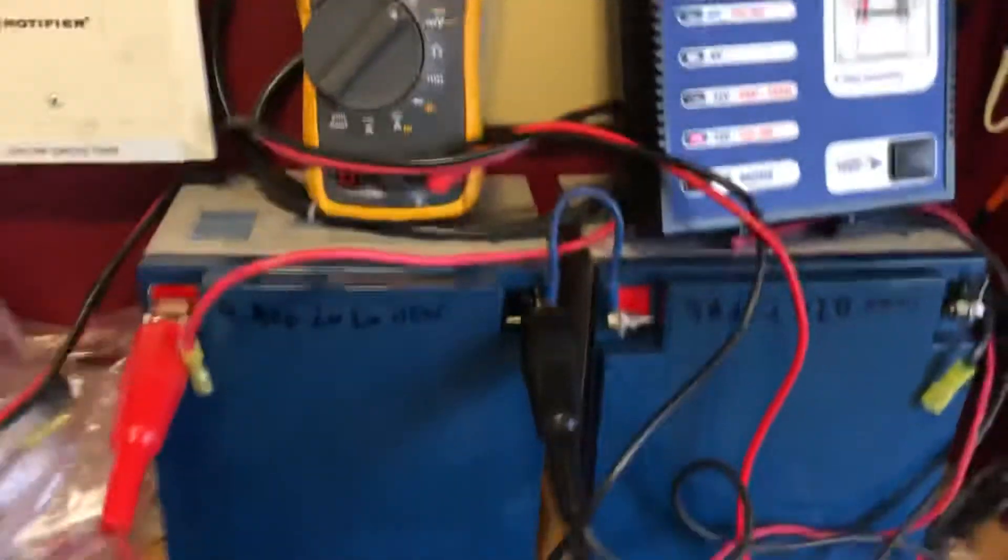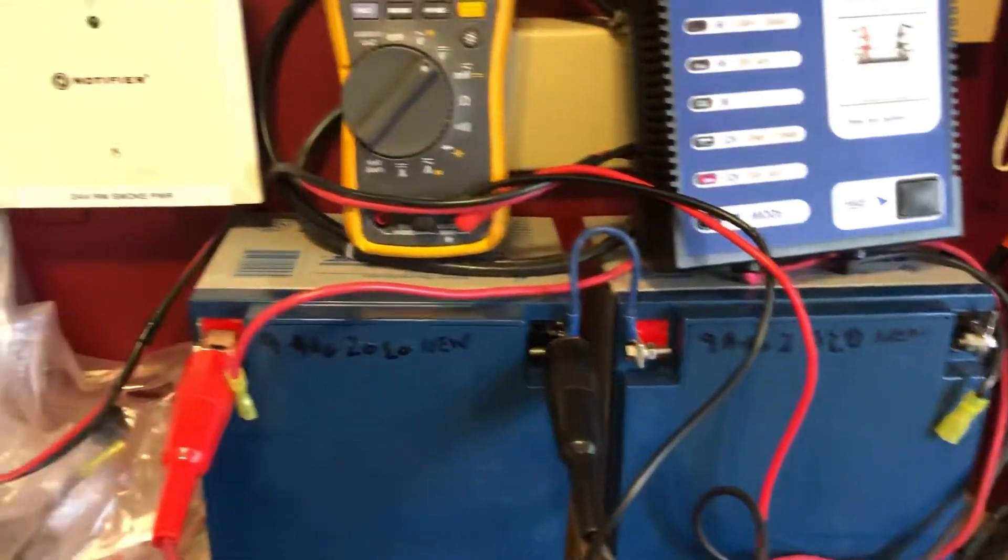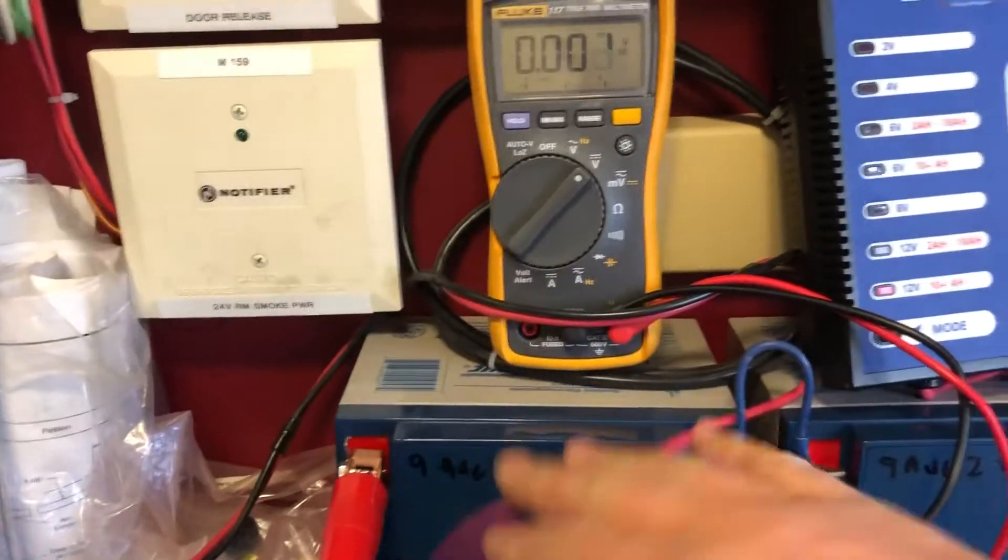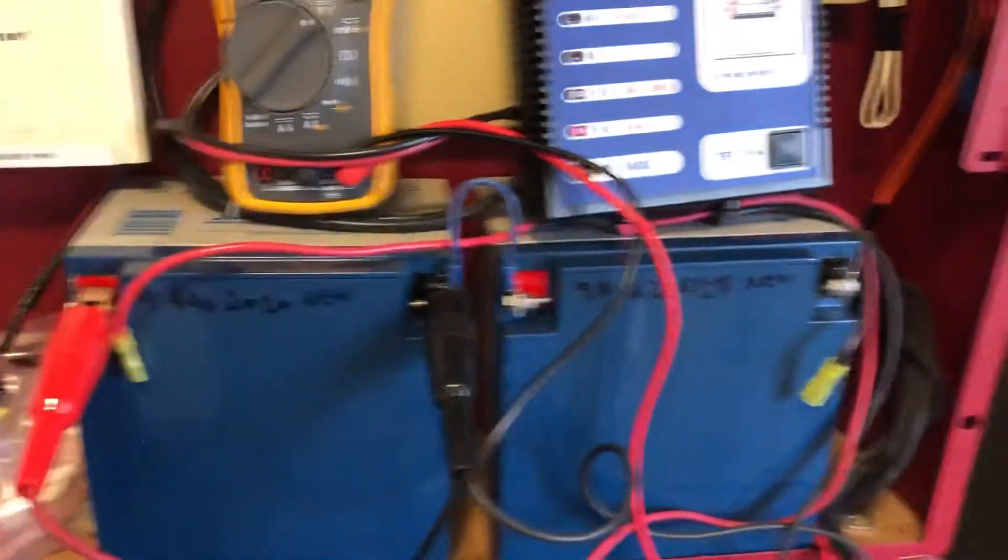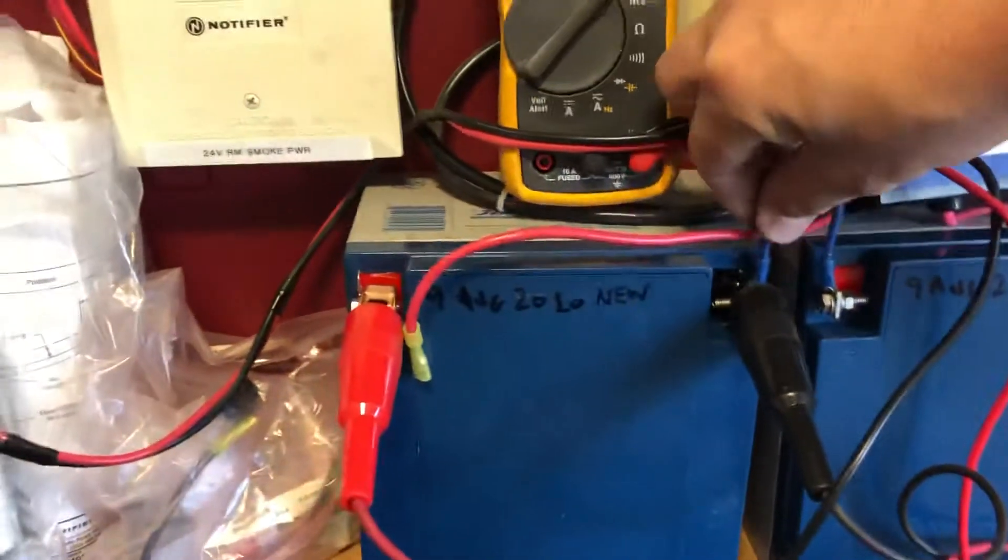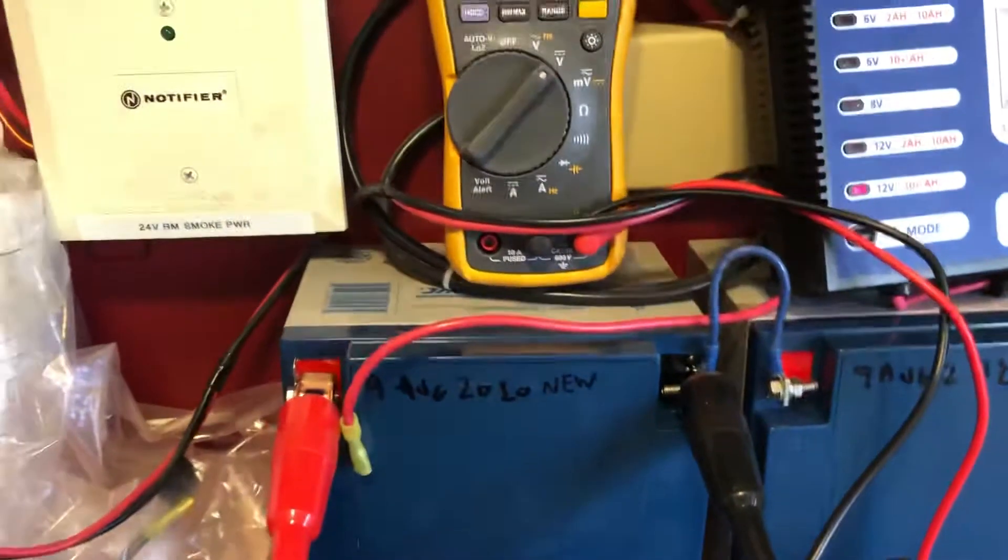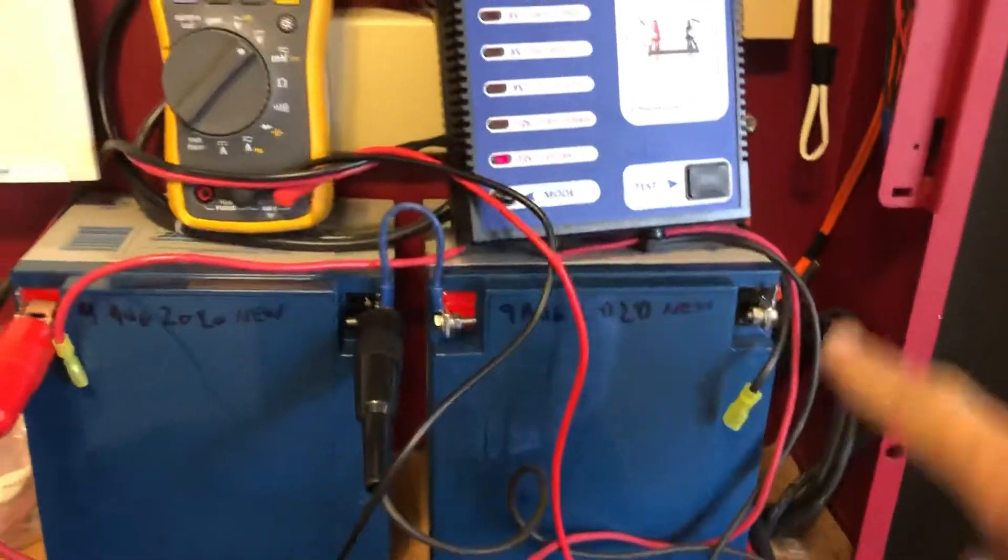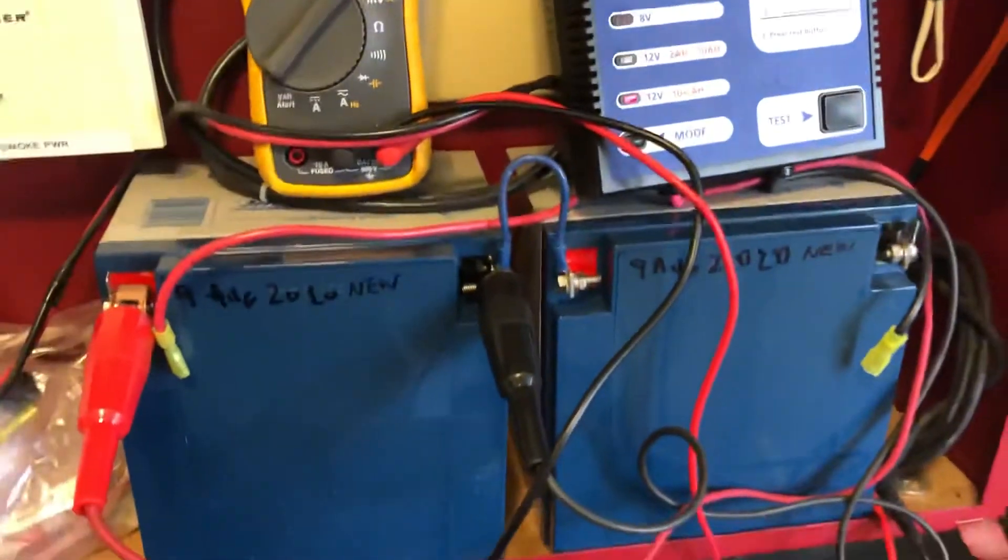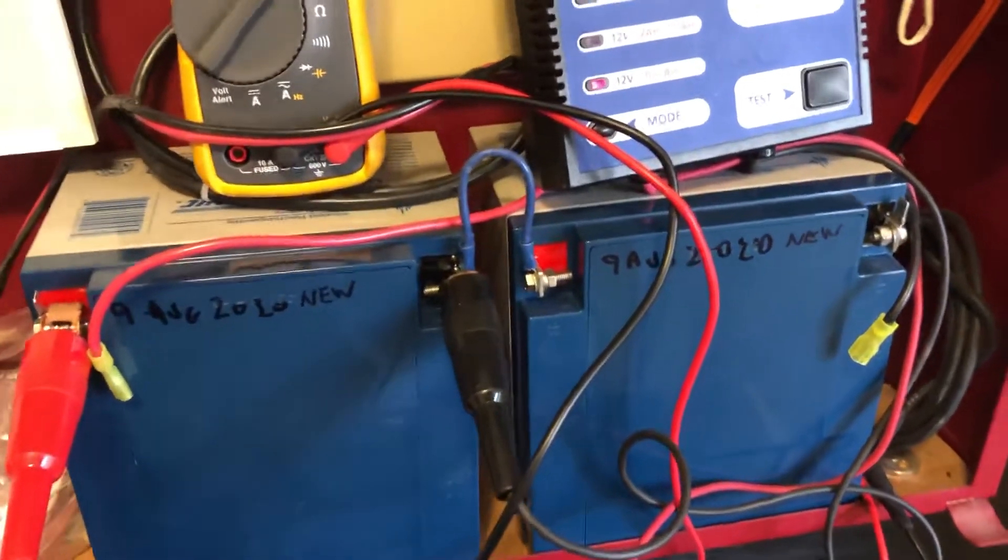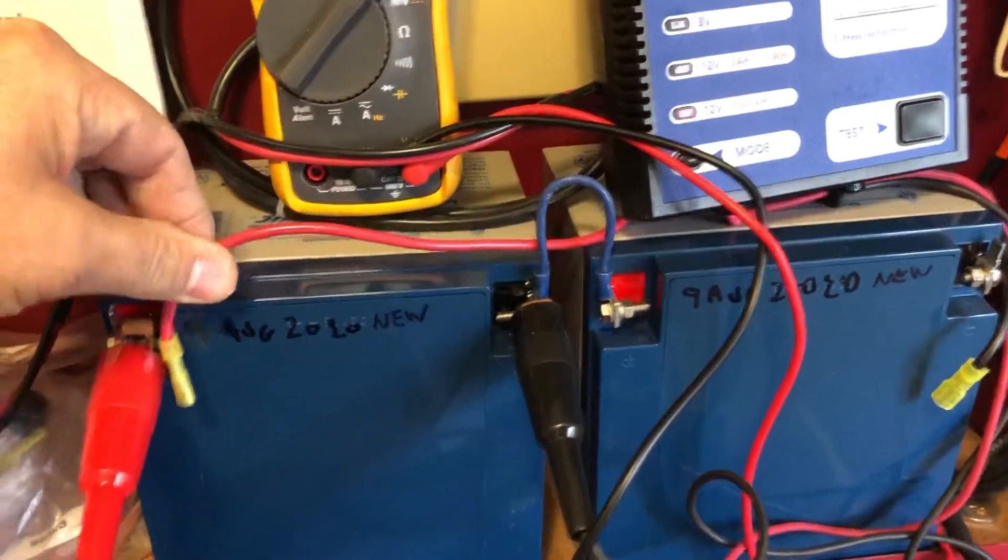First, what you want to do when you're load testing batteries, make sure at least, well I always do both my leads off the main panel. If it's easy I can just pull the second one off, but as long as this isn't going back into the panel, both leads are broken on each side coming in from the charger.